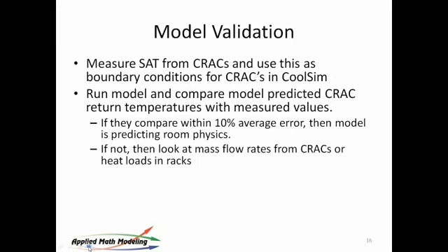Then we run the model. We compare the predicted CRAC return temperatures with the measured values. And if they compare within 10%, then the model is predicting the physics in the room fairly well. If not, then you go back and take a look at your equation and say, why not?